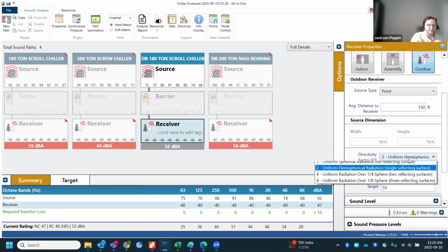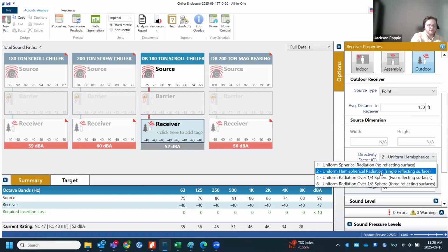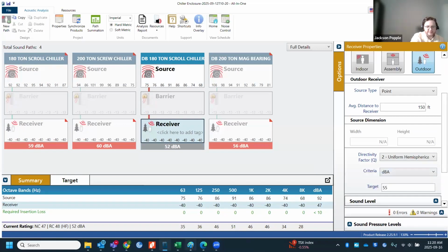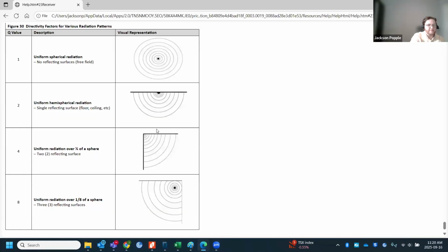It's also got this directivity factor of 2. If I pull this up, basically these should be kind of flipped. These are shown as they would be for duct systems, so think of this as the ceiling, but in our case we're looking at it for the floor. Basically, a directivity factor of 2 means your chiller or rooftop equipment is sitting on an open roof with nothing around it, which is hardly ever the case.